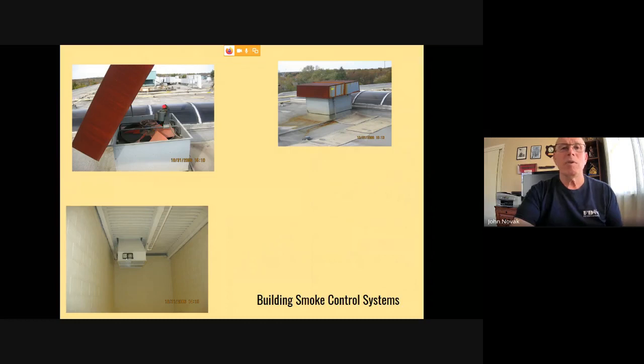So when the fire alarm goes off, this fan kicks on and starts to evacuate smoke from the atrium. The idea is to keep the egress path in the common area clear, so occupants can egress the building through hallways or corridors that are open to the atrium to get to a stairwell, to go down a stairwell to get out of the building.